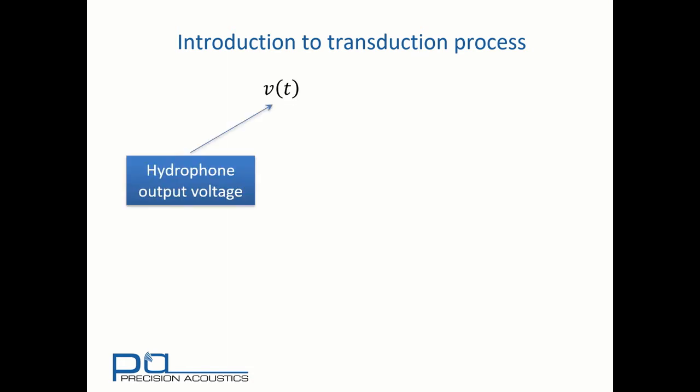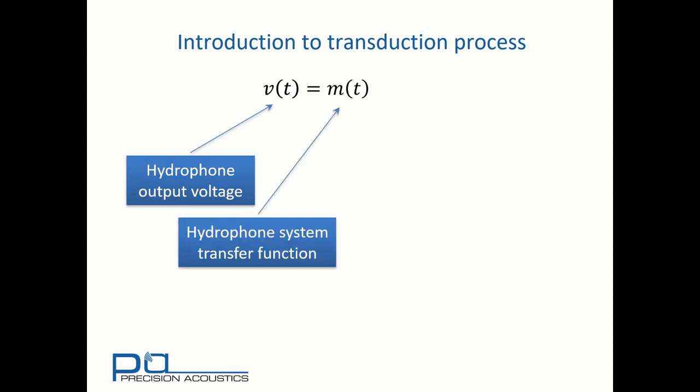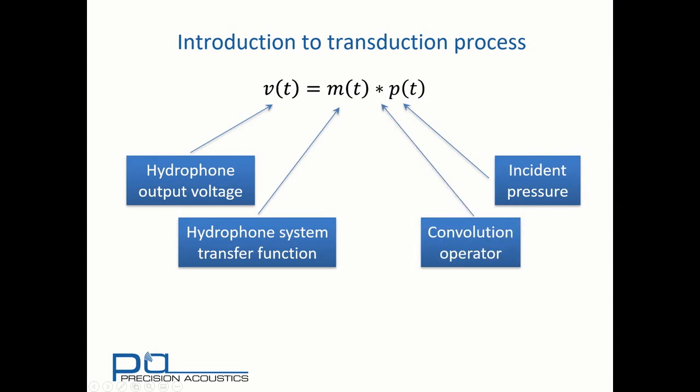When we connect a hydrophone to a data acquisition device, such as an oscilloscope, the waveform we measure is the hydrophone output voltage. This depends upon the hydrophone system transfer function and the incident pressure waveform that the hydrophone experiences, and these two quantities are convolved together.